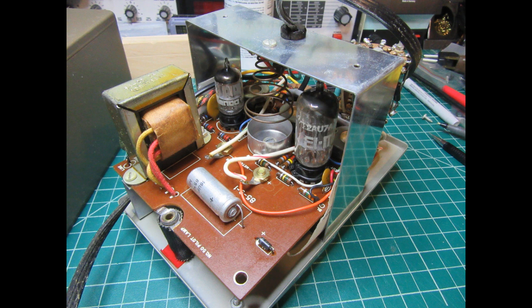To the right of the power transformer are basically 3 things. At the far right is a silicon diode. That's the only solid-state diode in the VTVM. And then an electrolytic capacitor, which is used as a filter. That diode and the capacitor are across the 120 volt secondary winding and produce a half-wave rectified and filtered DC voltage, which is used to power really all the circuitry in the VTVM, not counting the tube filaments and the pilot light.